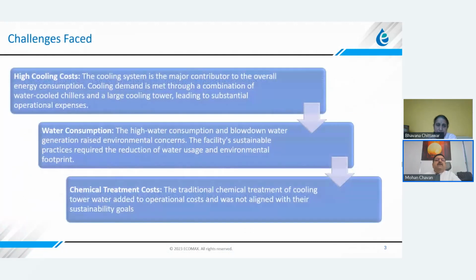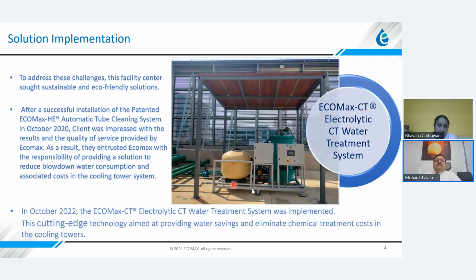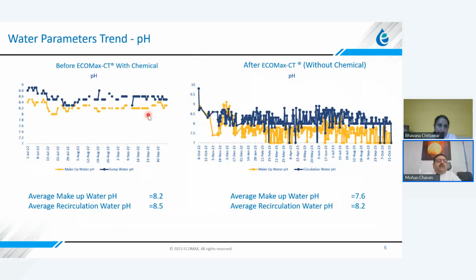This is for an office wherein the challenges were high cooling costs, high water consumption, and high chemical treatment costs. So this is the system that is installed on the terrace besides the cooling tower. Here, this blue line is before, and this is after. The pH of 8.2 was the makeup. Circulation was 8.5. Here the makeup pH was 7.6 after, and now circulation is maintained at 8.2, which is in the range.